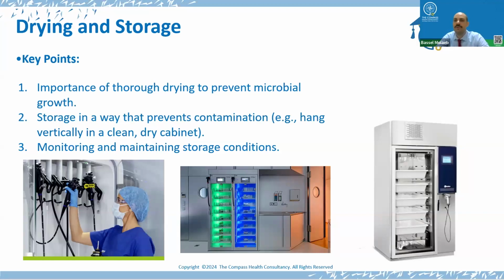Drying cabinets have been shown to reduce the risk of microbial contamination, so they are the best practice to be applied. Drying cabinets provide a controlled environment to help ensure that the endoscope channels remain dry. And if a drying cabinet is not available, the storage cabinet should have HEPA filtered air to allow circulation around the flexible endoscopes, and the flexible scopes must be dried prior to storage, as I mentioned. So endoscopes definitely should not be stored in shipment containers or cases.